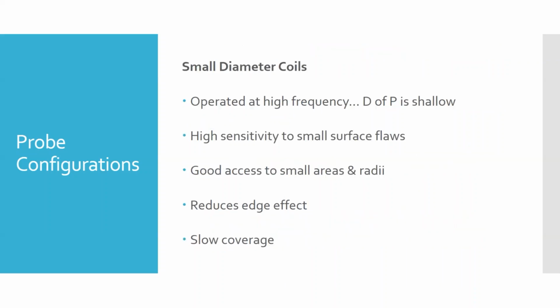The coils themselves can also be different sizes. Frequency is probably our biggest controllable variable, and certain styles or shapes of coils lend themselves better to different frequencies. Smaller coils tend to be operated at higher frequencies - they have a natural resonant frequency that works better with higher frequencies, but they don't produce as much depth of penetration. So they're really good for finding small surface flaws, since they also have high sensitivity.